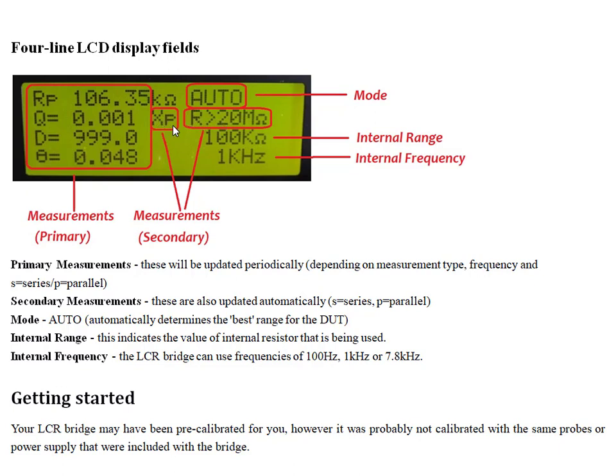It's reactance, and it's a parallel mode, so it's parallel reactance, and this is the reading, which in this case is too high, so it's just showing as greater than 20 megohms. And then you've got the range that it's using internally, and you've got the frequency it's using internally, which could be either 100 Hz, 1 kHz or 7.8 kHz.